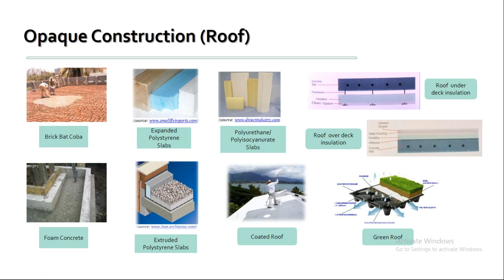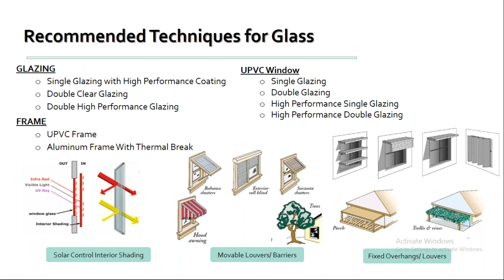You can also construct it with a green roof as well. And the recommended techniques for glass: you can use single glaze or double glaze, and it is preferable to use shading devices, movable louvers and barriers, which you can see on your screen, like fixed overhangs and louvers, horizontal overhangs, vertical fins, and deciduous trees. You can also use deciduous trees on the west side of your building, so that at sunset time it will help you to circulate fresh, cool air inside the building.